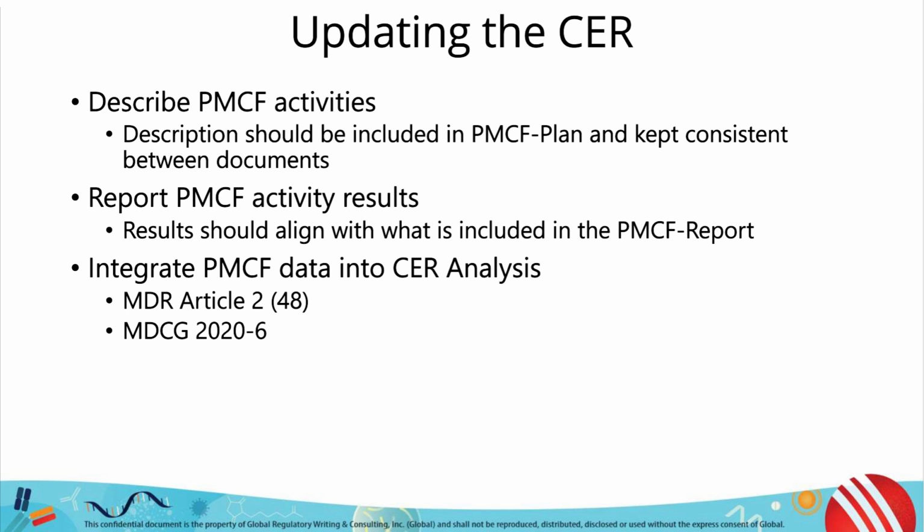From the PMCF plan, the CER should be updated with a clear description of PMCF activities and their purpose. And from the PMCF report, the CER should capture data that results from PMCF activities. If possible, discuss data in relation to identified safety and performance objectives and thresholds. You'll want to compare any adverse events to adverse events identified in the IFU and risk documentation.